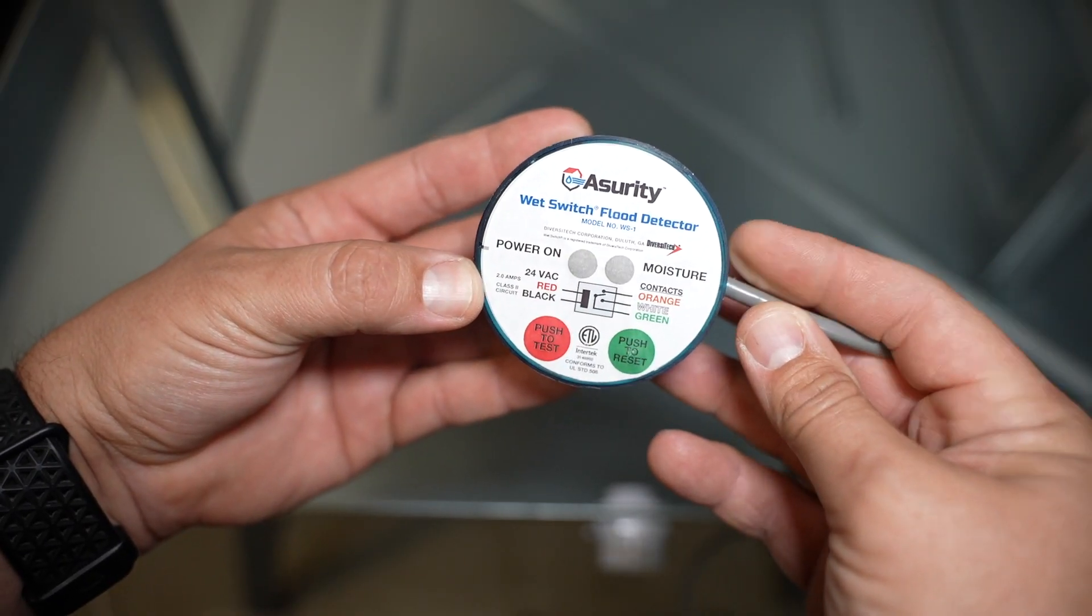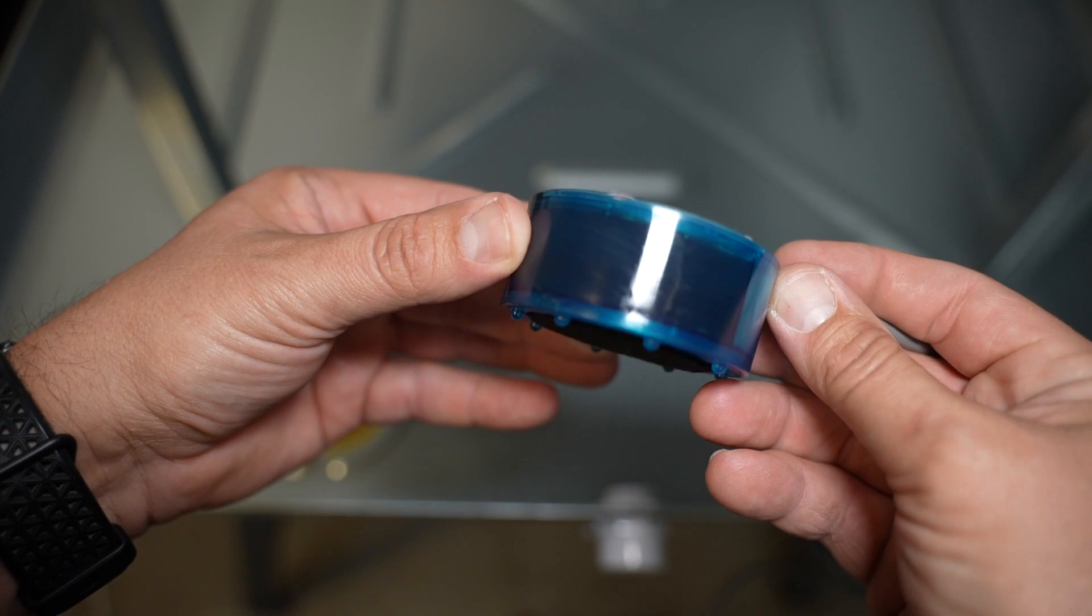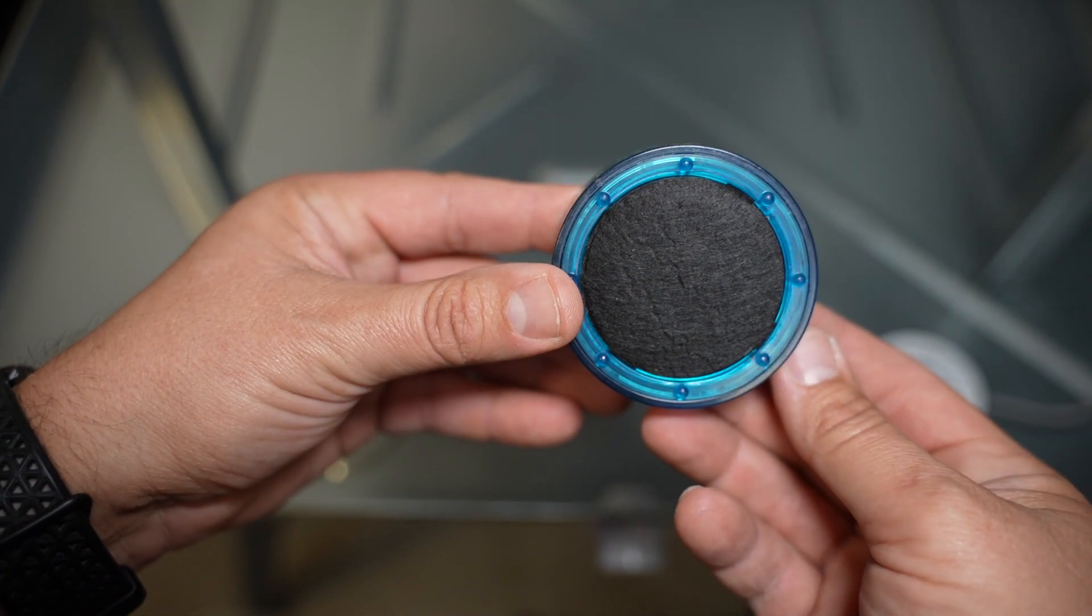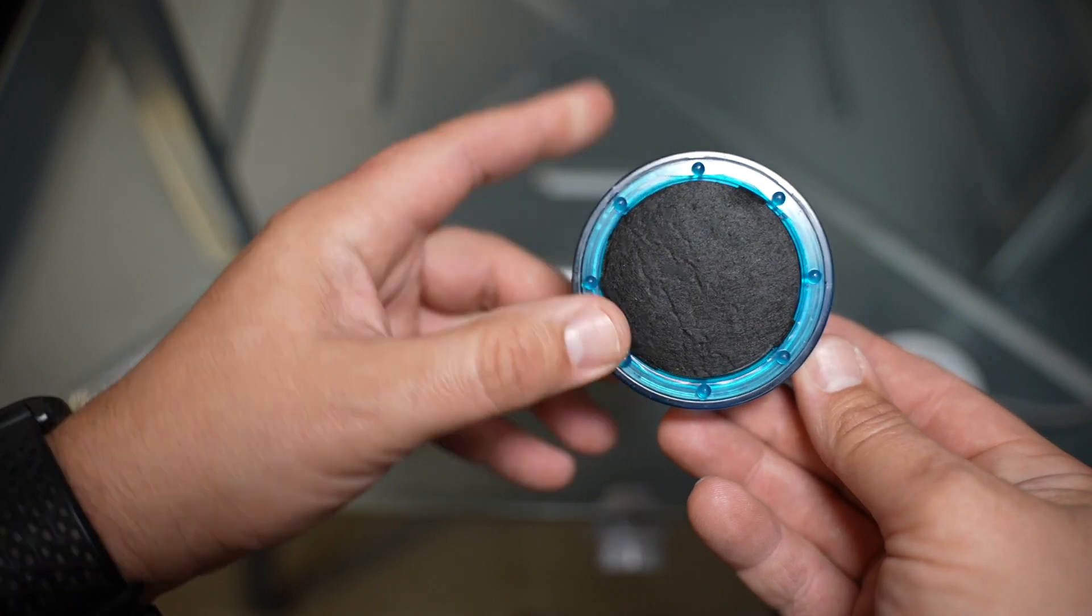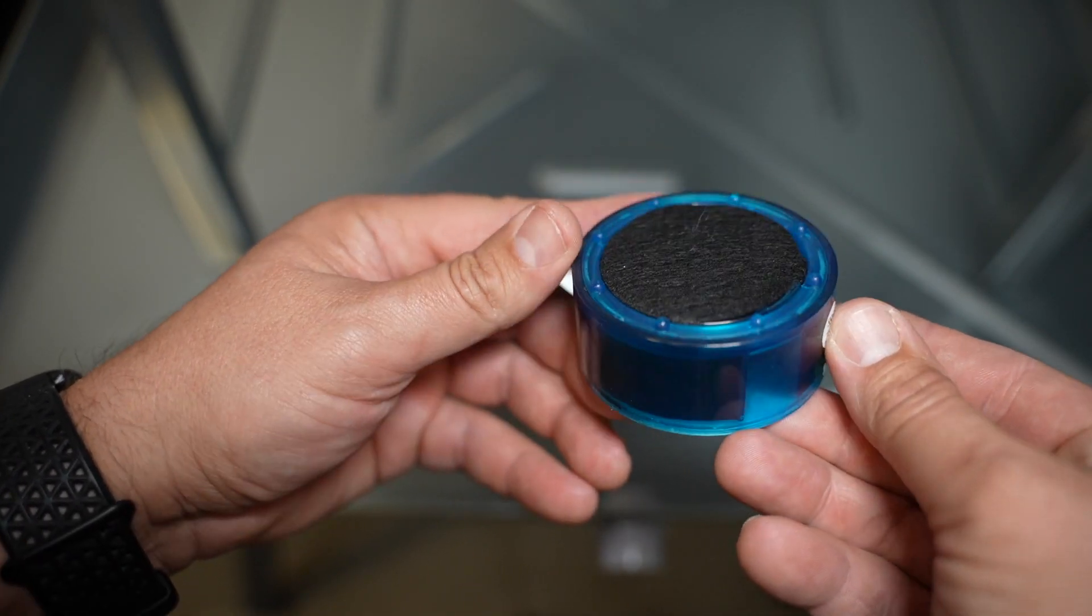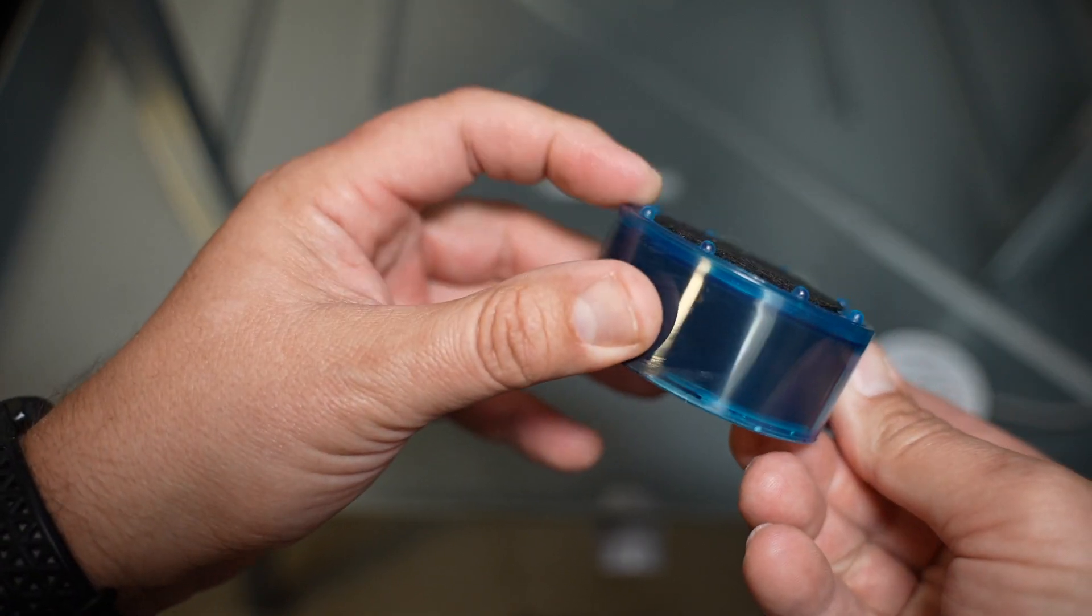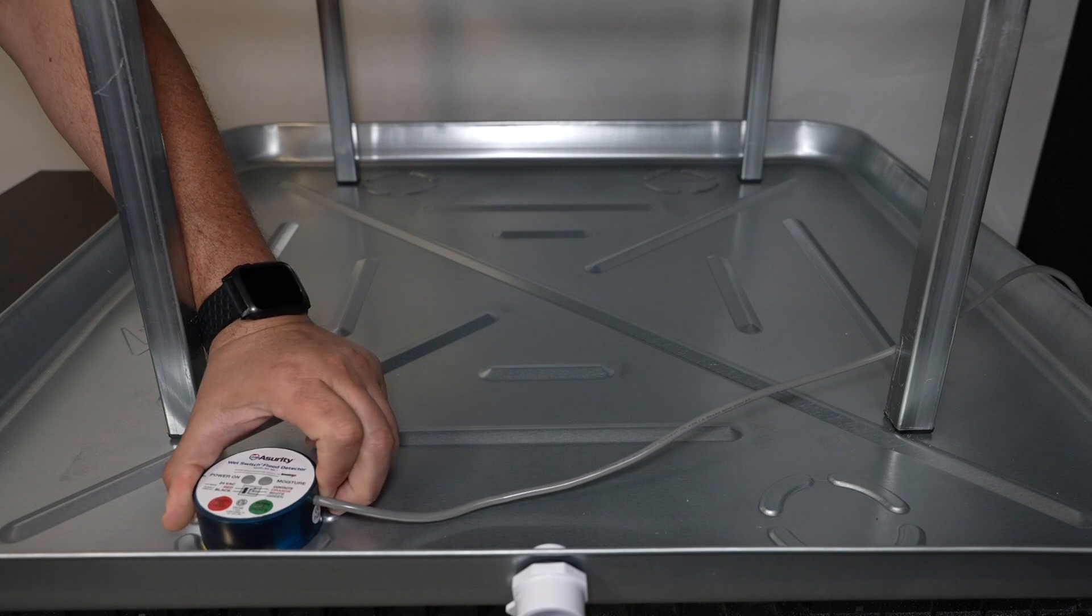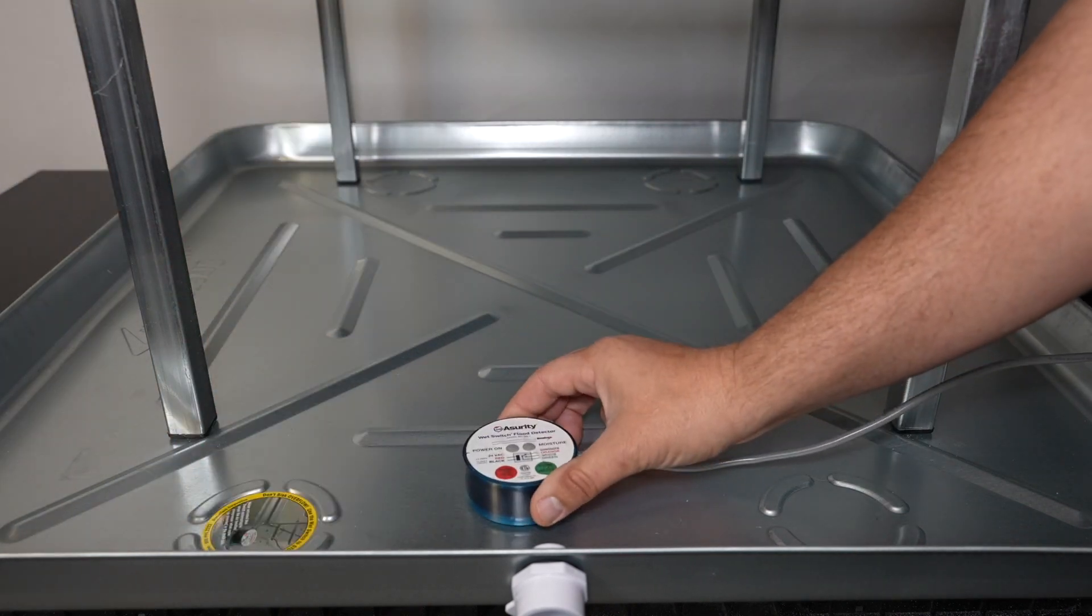When it comes to flood detection switches, the WS1 is the GOAT. Let's see why. The WS1 wet switch is a premium option for flood detection with solid state electronics and stainless steel sensors. The hydrophilic pad quickly draws water into the sensors, shutting equipment off with just a few drops of water. Its design makes it easy to install and allows for flexible placement options inside or outside of the pan.